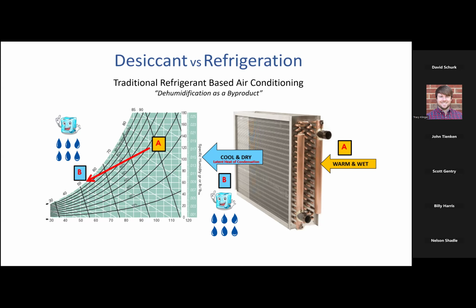And based on the temperature of the refrigerant or fluid that I supply to the coil, I will create a certain coil surface temperature. The colder the fluid coming in, the colder the surface temperature, the more I can cool and dehumidify the air in this type of a system. So let's look at how it might work. Let's say this is a DOAS unit, 100% outdoor air, bringing in warm and wet air from outdoors and cooling it and providing it to a space. And we can see as I take that warm and wet air through my coil, what I end up with on the other side is cool and dry air and moisture condensation typically forming on the fins, falling into the drain pan and being removed from the building. And that's how I dehumidify the air in a traditional cold surface condensing type system.